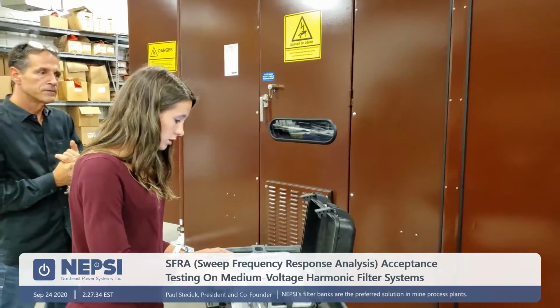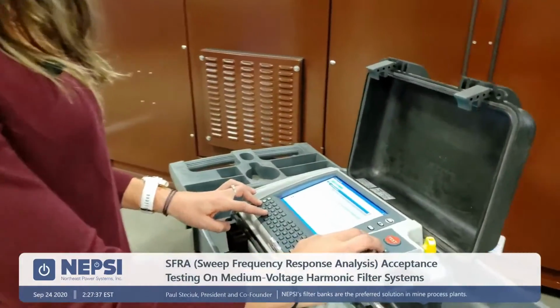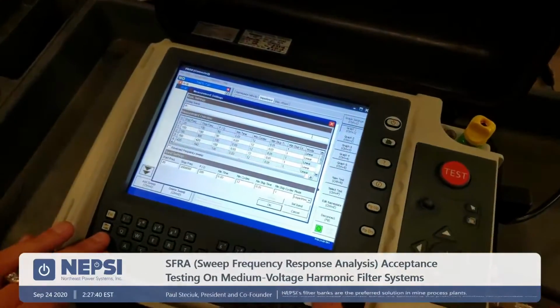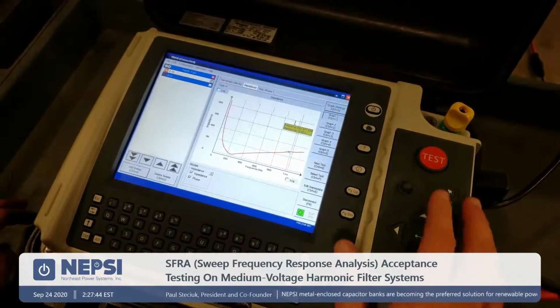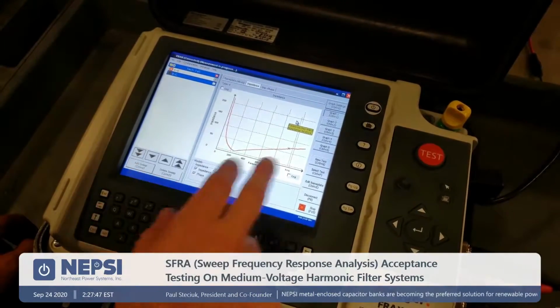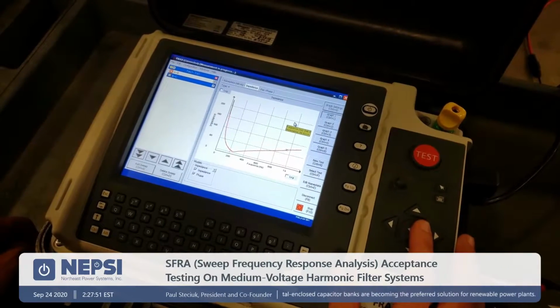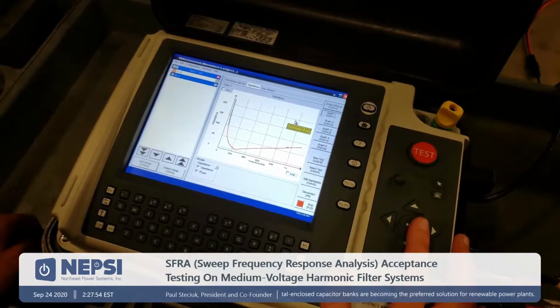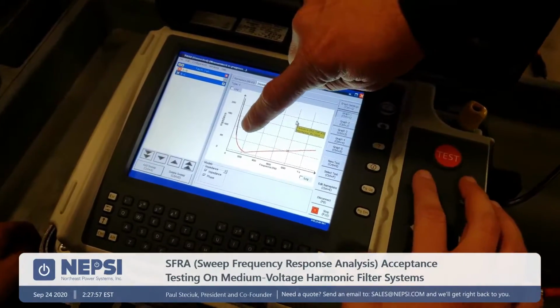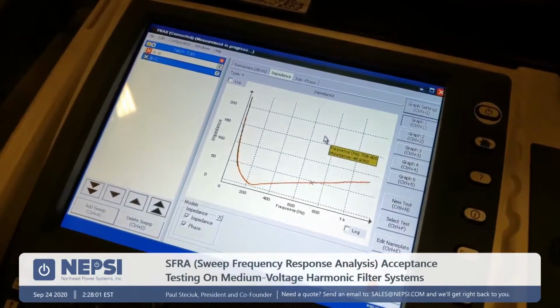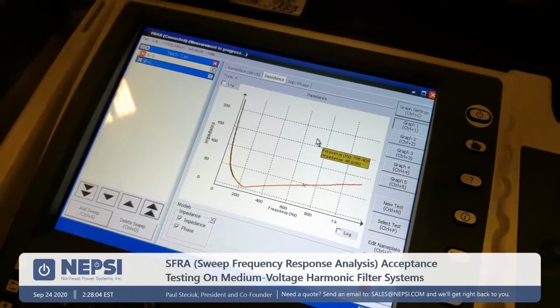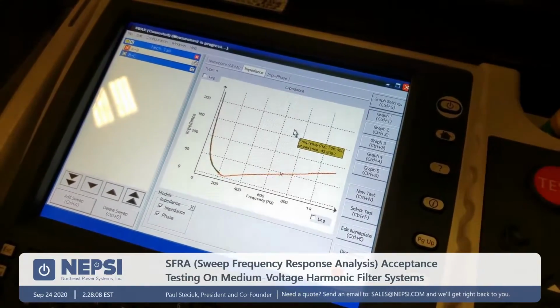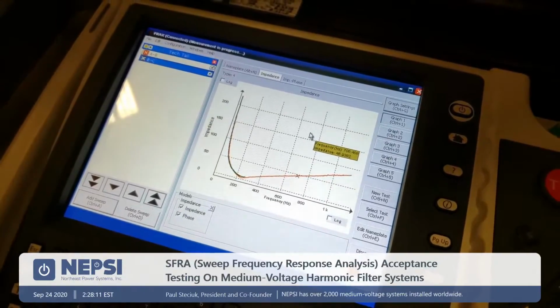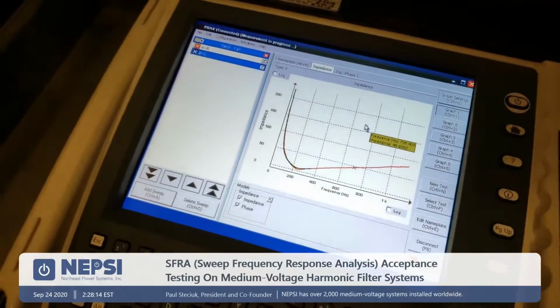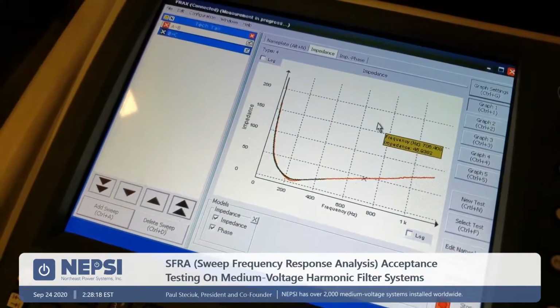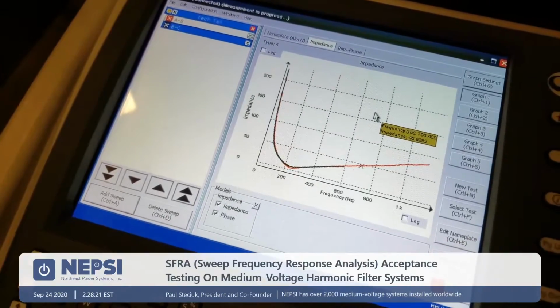So if I just go in here and rename this because we're on A to C, or we're on BC or AC? BC. So rename that BC, and then we'll run that test, and this should look exactly like phase AB. So if you zoom in, you can actually see the scan. One overlays on top of the other. So if there was say the wrong number of capacitors in this setup that we've assembled, it would show itself right now on the C phase. It would show as a shift in frequency, right? Yes, the actual tuning point. The tuning point would shift at the bottom, right at that minimum point. You would see a difference.